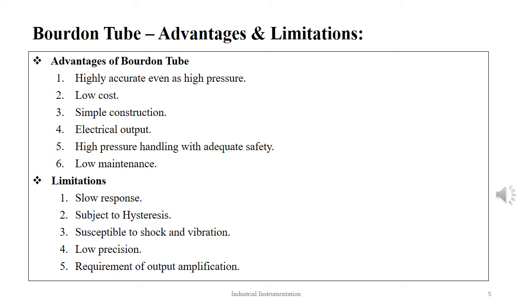There are a few limitations of the Bourdon tube, which are that their speed of response is pretty slow. The device is affected by hysteresis errors. The device is susceptible to both shock and vibration. A certain level of output amplification is always needed for good interpretable readouts, and the precision in measurement of the device is on the lower side.